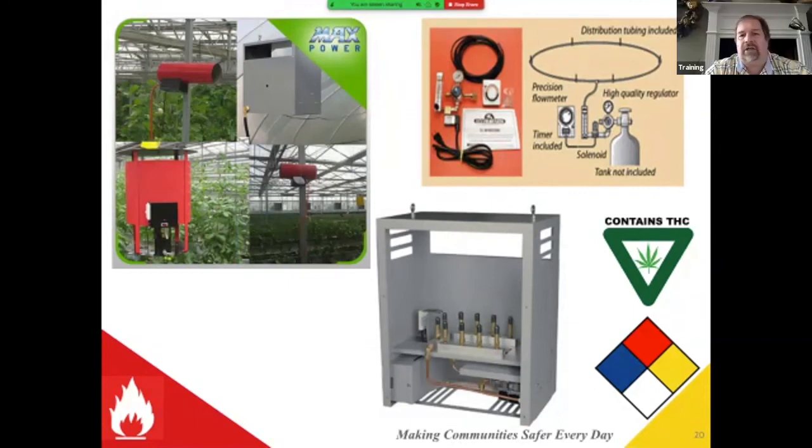Yeah, I agree. You have to take the most stringent, obviously, and you have to follow the code minimum. The only place you can't follow the code minimum is when the code directly conflicts with the listing of a piece of equipment and makes that equipment operation unsafe, which you're not going to find in this application. But yeah, it's typically the most stringent shall govern when you weed your way through the code hierarchy. The ones that are the most deficient in their instructions are the unlisted ones, which I have not approved to date anyways.